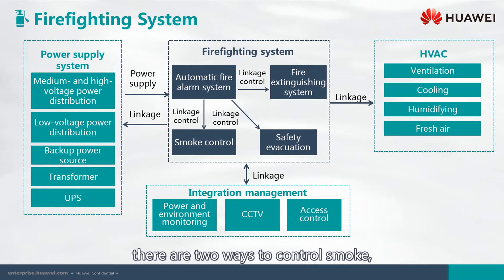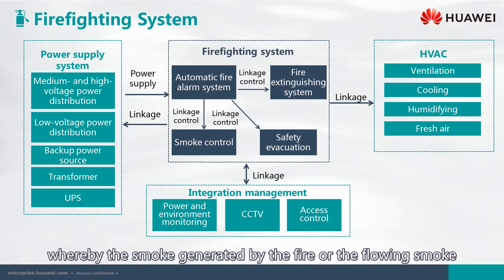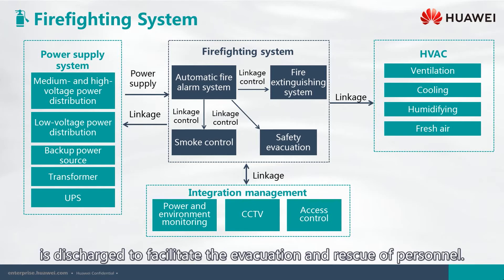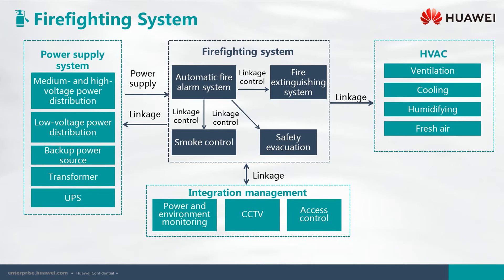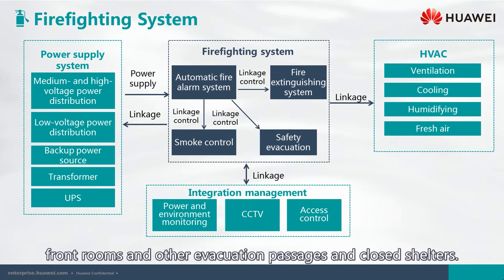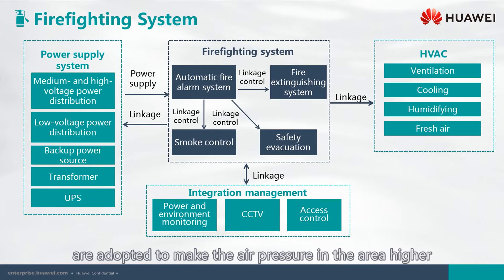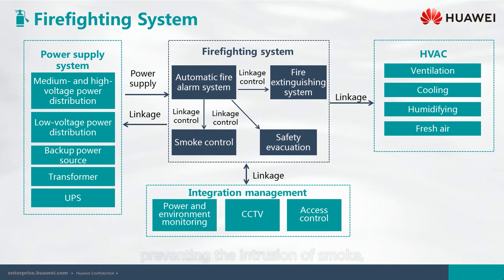There are two ways to control smoke: smoke exhaustion and smoke prevention. Smoke exhaustion is mainly for the fire area, whereby the smoke generated by the fire or the flowing smoke is discharged to facilitate the evacuation and rescue of personnel. Smoke prevention is mainly for non-fire areas, especially stairwells, front rooms, and other evacuation passages and closed shelters. Mechanical air pressure supply and smoke prevention measures are adopted to make the air pressure in the area higher than the air pressure in the fire area, preventing the intrusion of smoke and controlling the spread of fire.